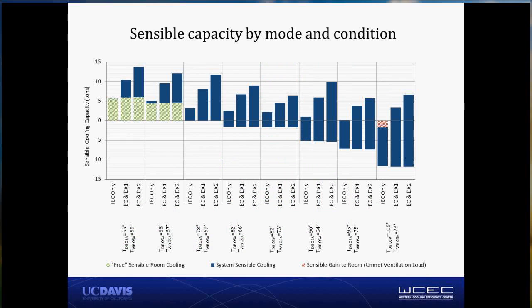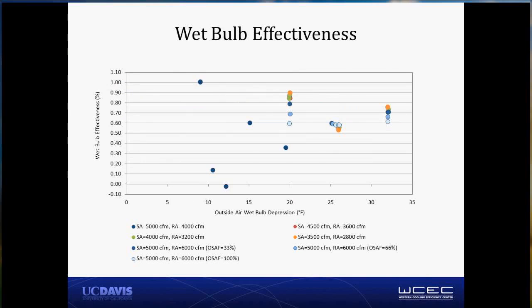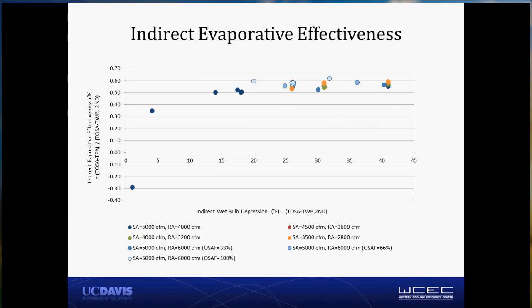I'm going to skip through a couple of these slides just for the sake of time, but you can see that we've mapped out the performance of this equipment to very, very clear marks. We're using a metric we call the indirect evaporative effectiveness to describe sort of the wet bulb effectiveness of this machine. It's the same in concept, except it's using the wet bulb temperature at the inlet from the return air from the inlet to the secondary stream, because really that is the theoretical driving potential for this indirect evap system. And relative to that number, it's achieving about 60% effectiveness. Good.